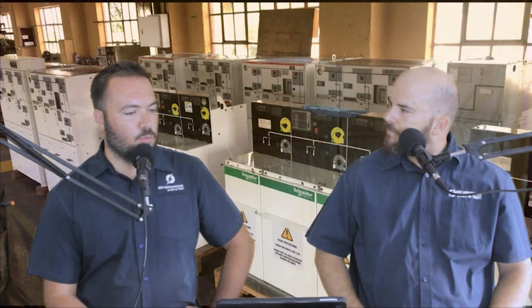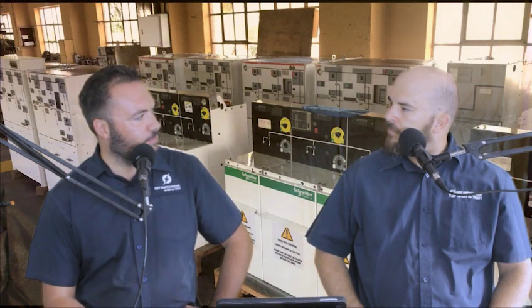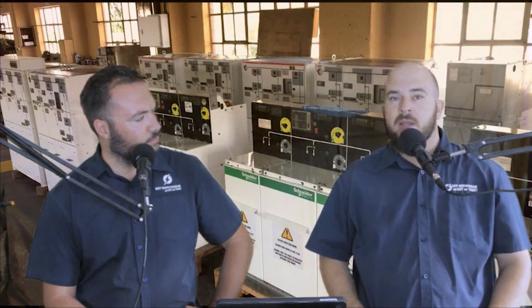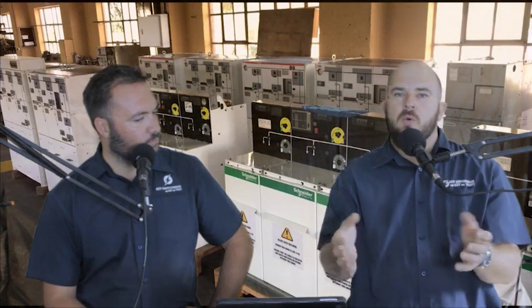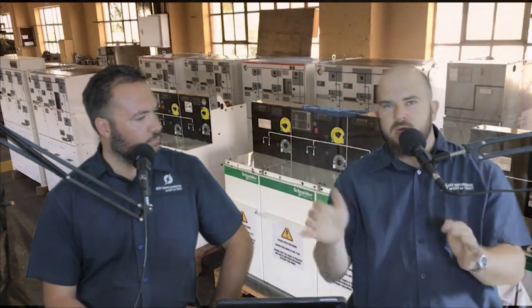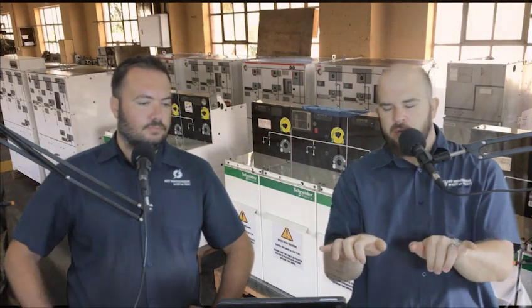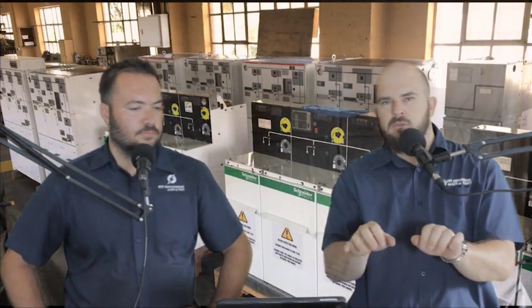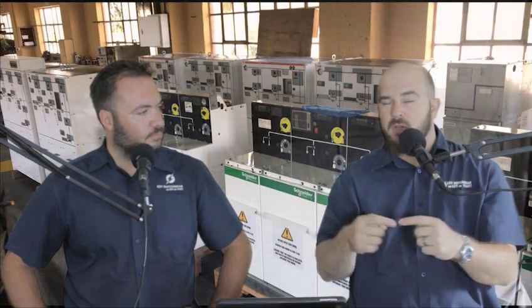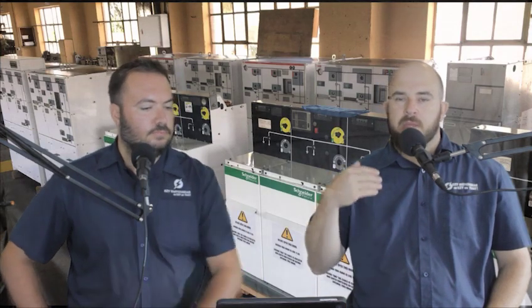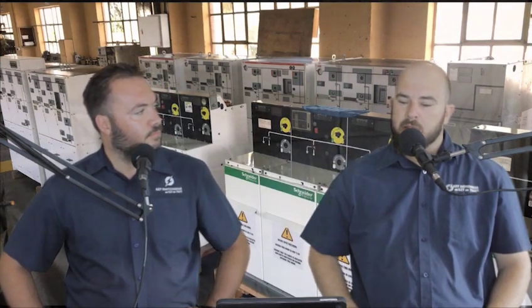Okay. And then in what instance will you use a bus section? So a bus section is a way to break up a board where you have more than one source, or where the fault current of the combined sources is too high. Then you would use a bus coupler to make sure that you cannot have a short circuit on both, feeding into the same fault level, which would then be much higher than what the switchgear can handle.